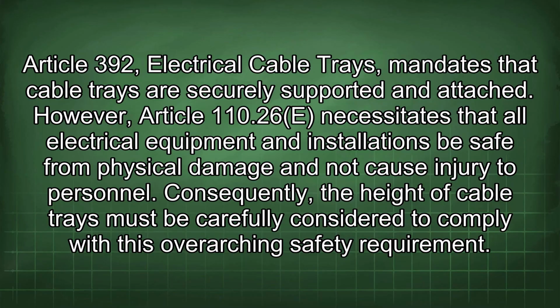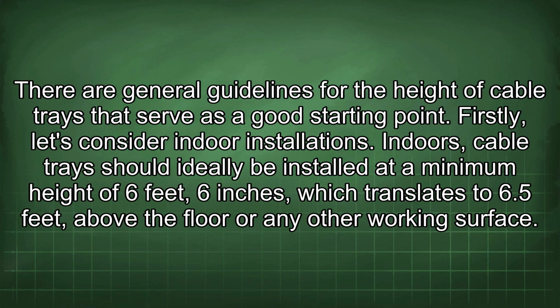Article 392, Electrical Cable Trays, mandates that cable trays are securely supported and attached. However, Article 110.26(E) necessitates that all electrical equipment and installations be safe from physical damage and not cause injury to personnel. Consequently, the height of cable trays must be carefully considered to comply with this overarching safety requirement. There are general guidelines for the height of cable trays that serve as a good starting point.